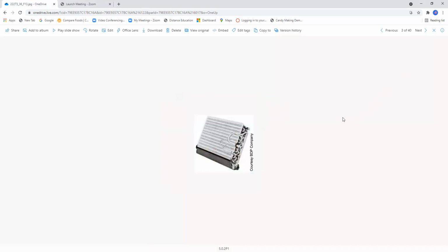This is a slant coil design. I've seen these a lot on Carrier BDP products. They work reasonably well. The only thing I have an issue with on these is that if they're not mounted in the correct position, some of the moisture may not run off and collect in this drain pan, and it ends up in the floor of the return air cavity and creates moisture and mold issues. Airflow is very critical on this slant coil design.